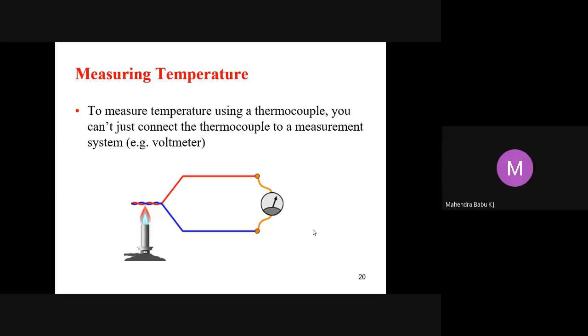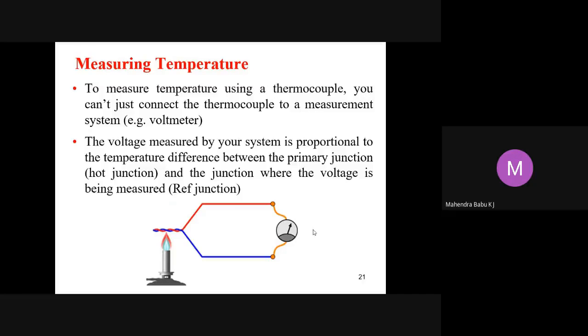To measure temperature using a thermocouple, you cannot just connect the thermocouple to a measurement system, that is, a voltmeter. Then what do you need to do? The voltage measured by your system is proportional to the temperature difference between the primary junction, also called the hot junction, and the junction where the voltage is being measured, called the reference junction.